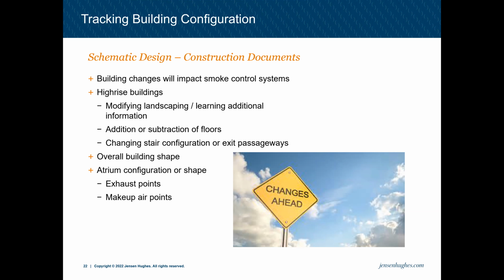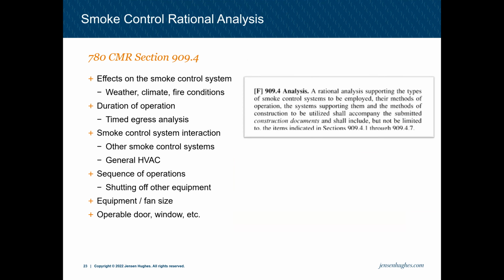So if you have an atrium and you start to tinker with where the exhaust is coming from or where the makeup air is coming from, a lot of times that might be conflicting with a security protocol or some exterior facade that can impact the atrium smoke control system. And being cognizant of that is really important. Next, what should happen, as we talked about, in the design development phase, usually is creating a smoke control rational analysis. It is required by code, but as we said before, it's also a great tool to ensure concurrency between every design group associated with a project.